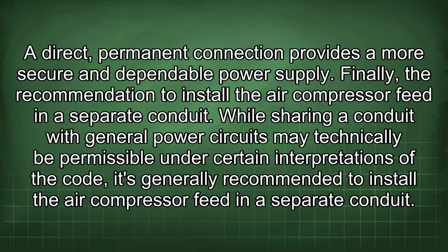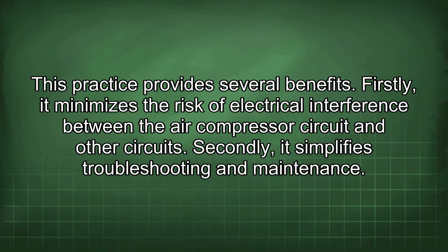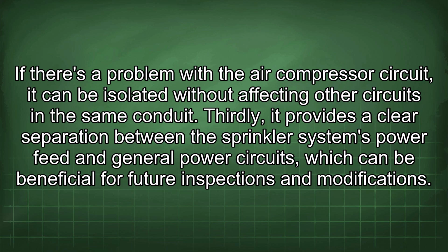Finally, the recommendation to install the air compressor feed in a separate conduit. While sharing a conduit with general power circuits may technically be permissible under certain interpretations of the code, it's generally recommended to install the air compressor feed in a separate conduit. This practice provides several benefits. Firstly, it minimizes the risk of electrical interference between the air compressor circuit and other circuits. Secondly, it simplifies troubleshooting and maintenance. If there's a problem with the air compressor circuit, it can be isolated without affecting other circuits in the same conduit. Thirdly, it provides a clear separation between the sprinkler system's power feed and general power circuits, which can be beneficial for future inspections and modifications.